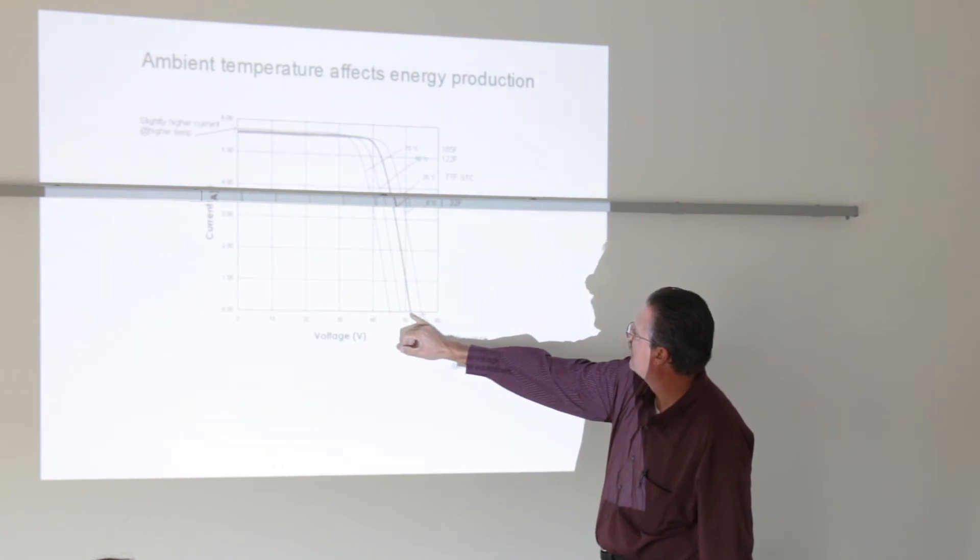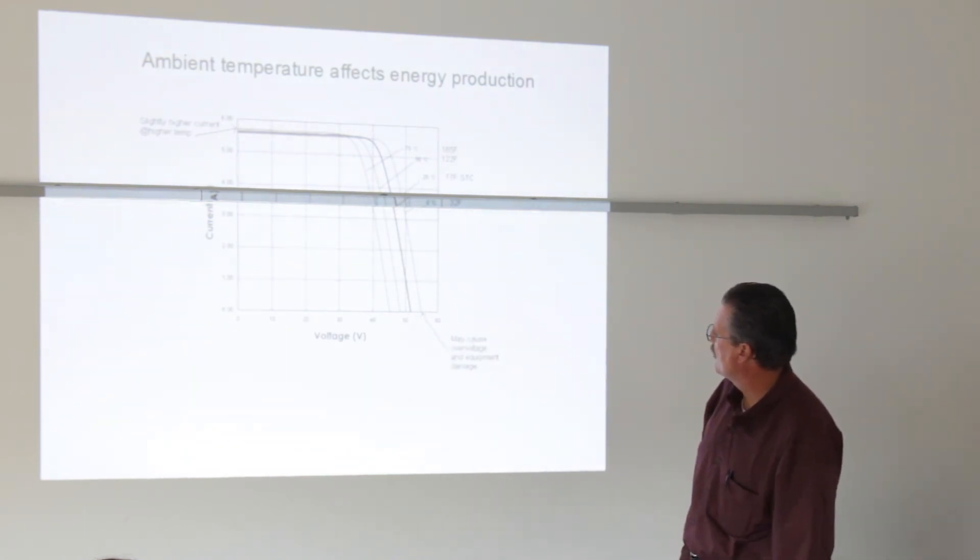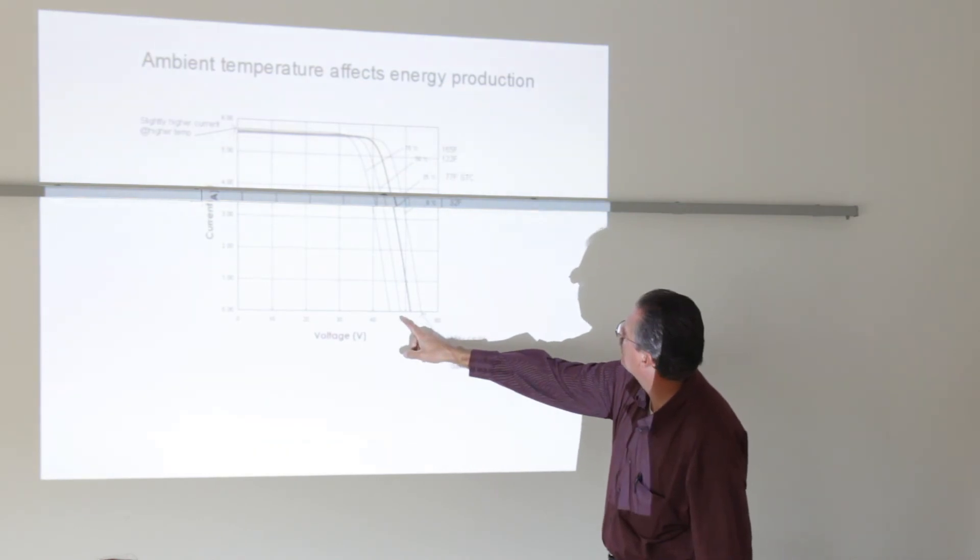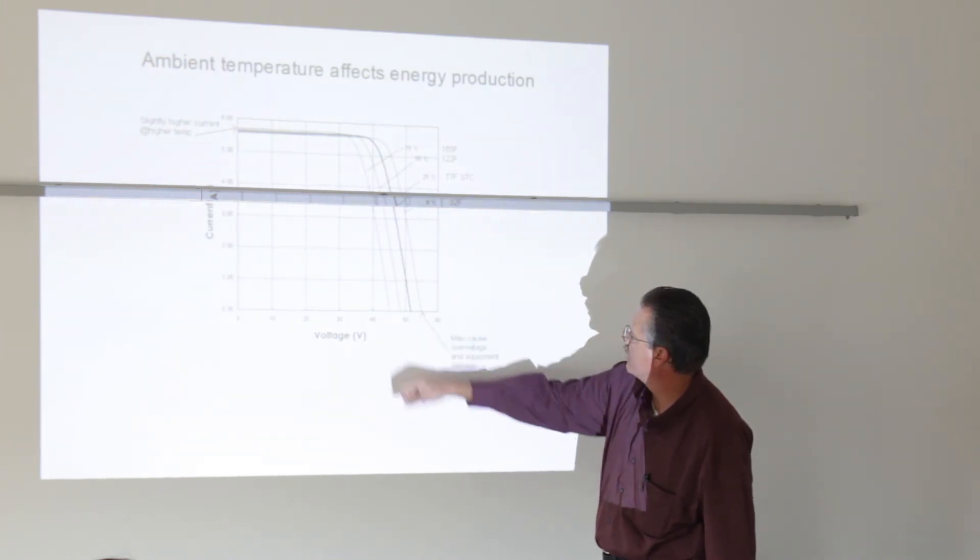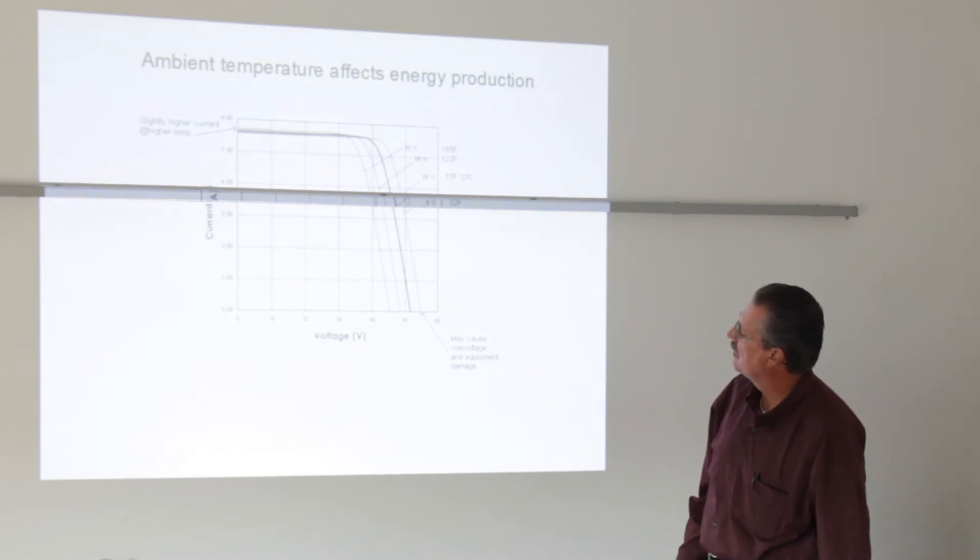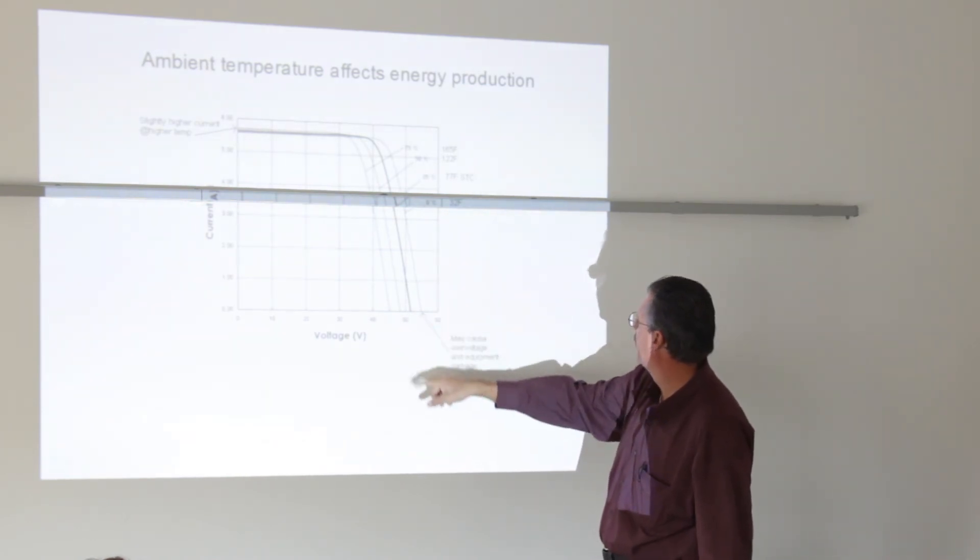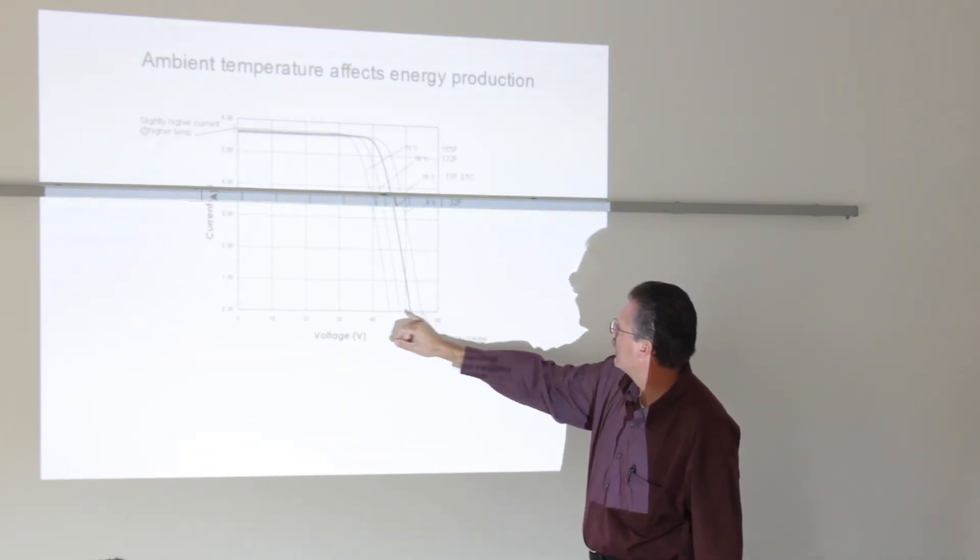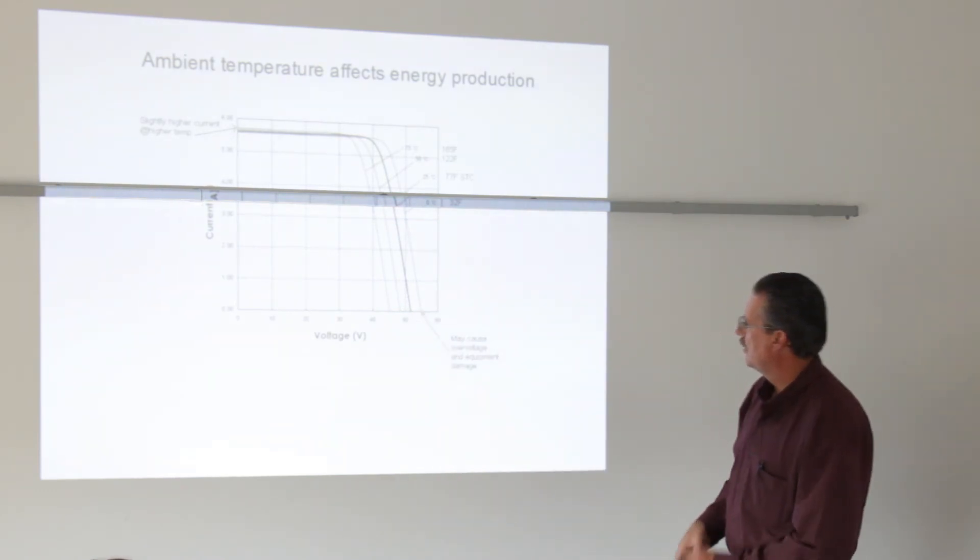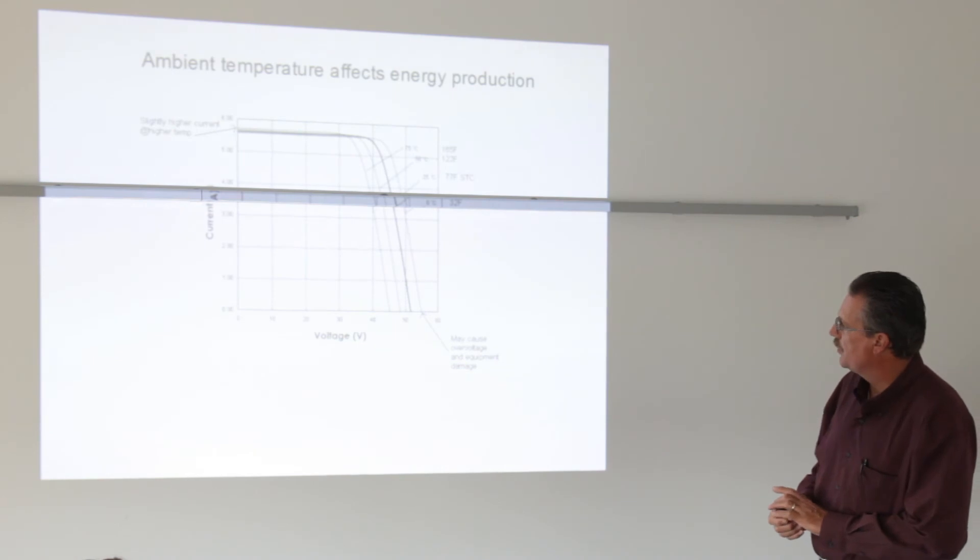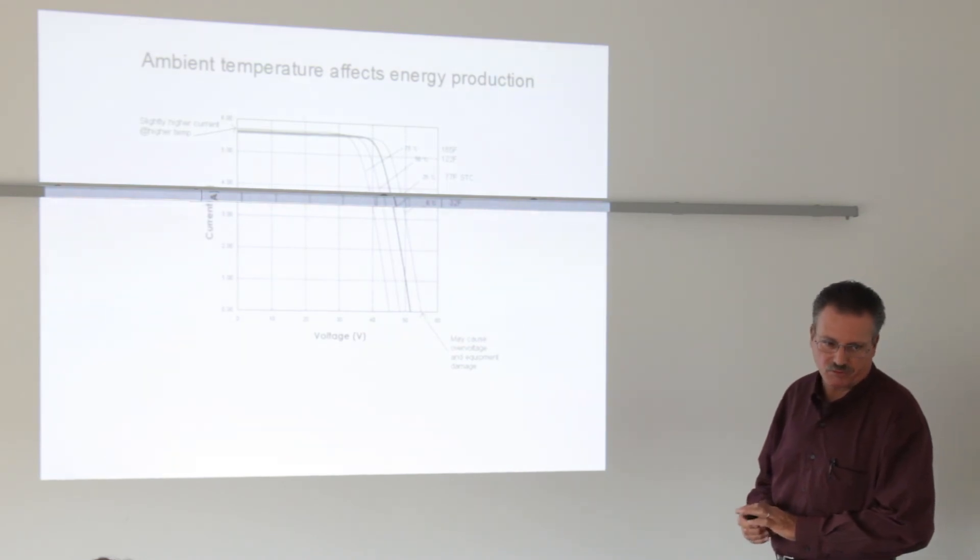That is a standard of testing. And we have that by the dark line here. So as an example, this module puts out, say, 52 volts at 77 degrees. At 165 degrees, which is a very warm rooftop temperature, it can get into the mid-40s. So you'll have a decrease in energy production. In fact, if it's hot enough, it may not even start the inverter up if it falls outside the operating window for that inverter. At 32 degrees, it is going to be in the mid-50s. So you're looking at almost a 10-volt difference in voltage where in the wintertime you could actually cause an over-voltage condition.